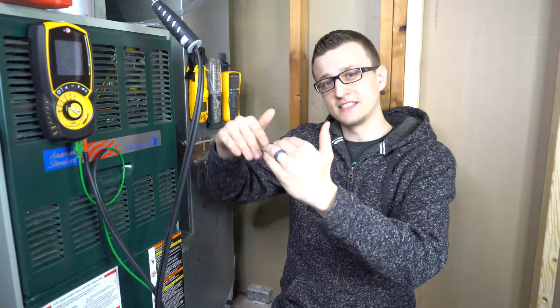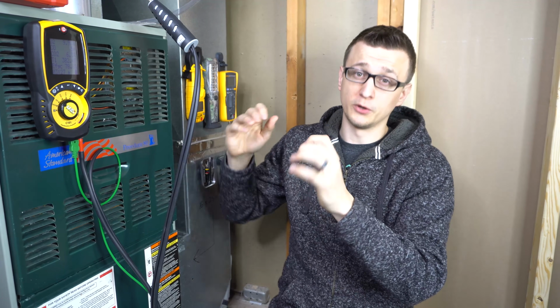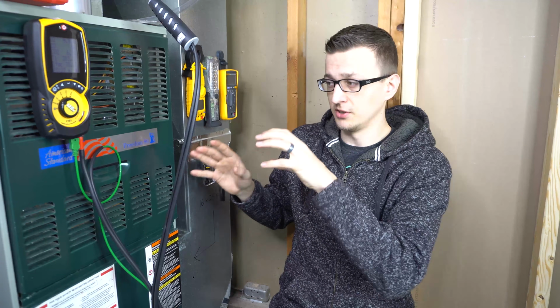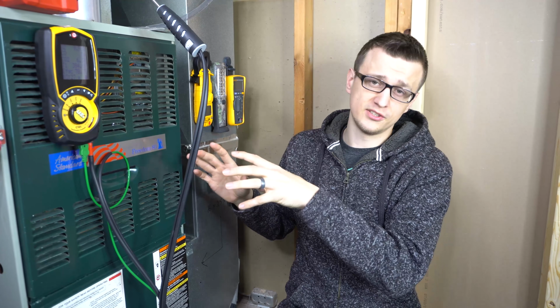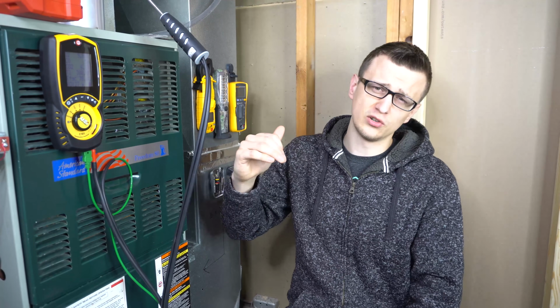If the carbon monoxide is getting to 200, then we for sure need to do some investigation, because there's definitely something going on that's causing the carbon monoxide to go higher. And just so you know, newer furnaces generally have lower carbon monoxide levels or carbon monoxide emissions, whereas older furnaces generally have higher levels of carbon monoxide.